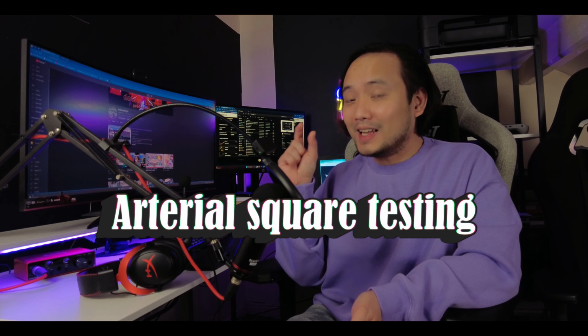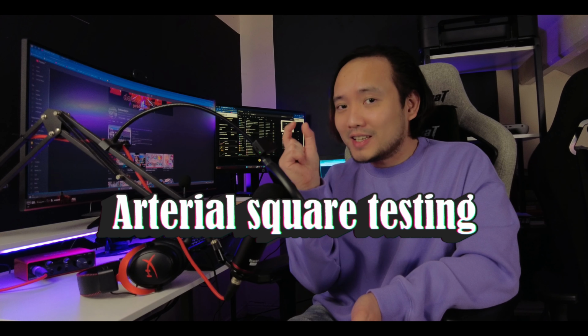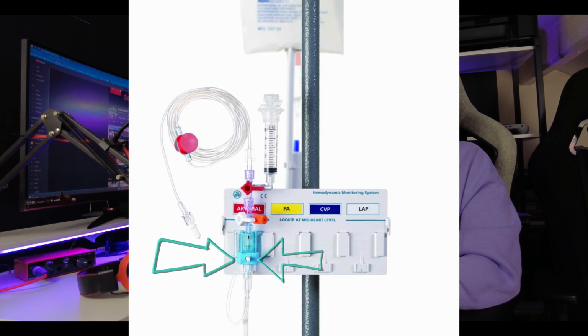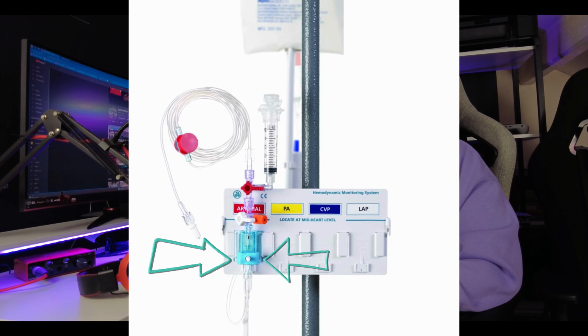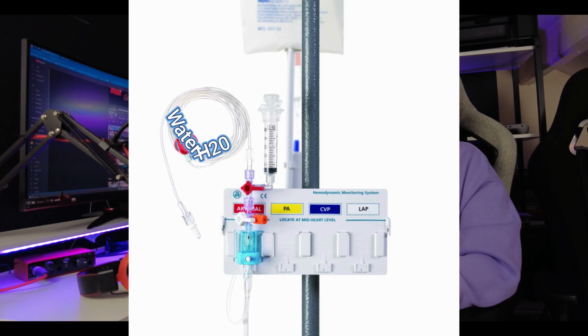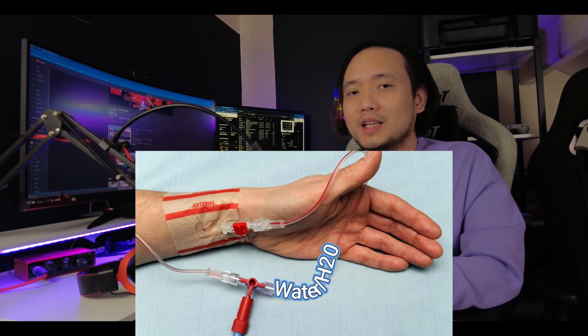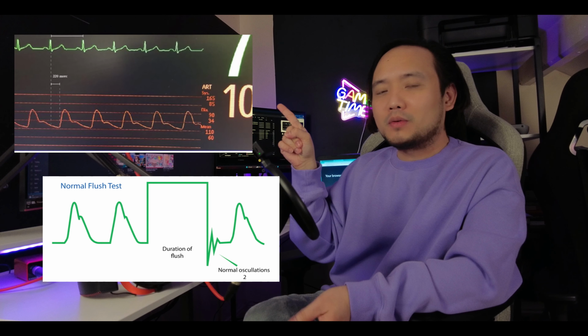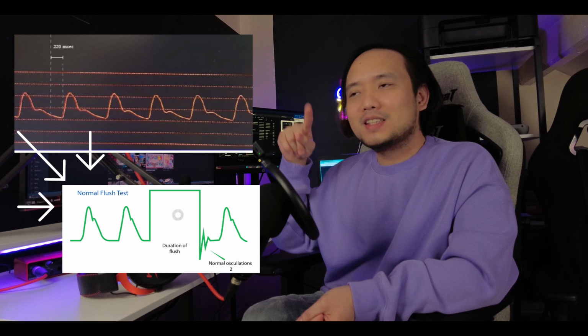The square test is something that we do like a flush. Again, that transducer, we squeeze it, and once we squeeze it, it's going to flush fluid directly to the arterial line and it will just deliver fluid. But what we test there is what will show in the monitor. That is a picture of a square test. As you can see, it's not totally a square.